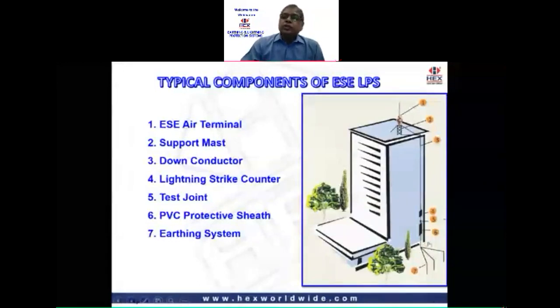The standard also states that if the overall height of the structure is more than 28 meters, then two down conductors must be installed for each LA, and each down conductor must have two or three earth pits each.